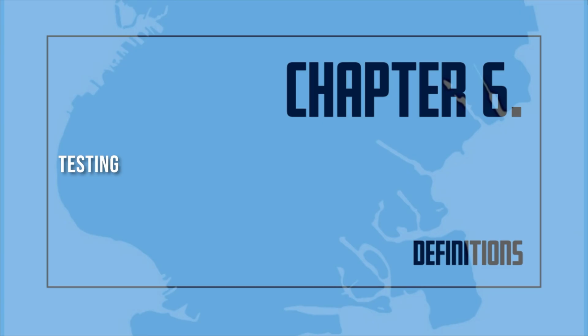Testing. A procedure used to determine the status of a system as intended by conducting periodic physical checks on water-based fire protection systems, such as water flow tests, fire pump tests, alarm tests, and trip tests of dry pipe, deluge, or pre-action valves. These tests follow up on the original acceptance test at intervals specified in the appropriate chapter of the NFPA No. 25, 2002 edition.